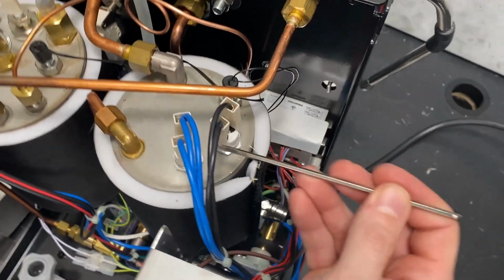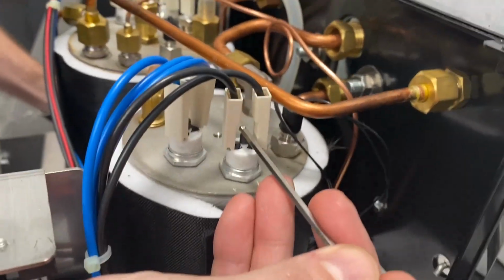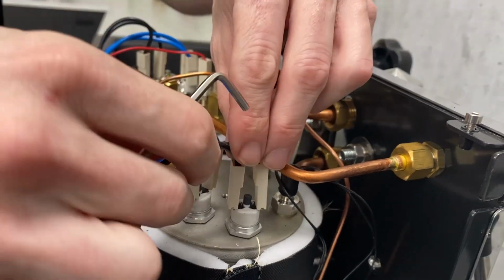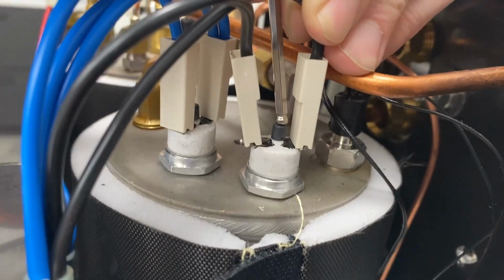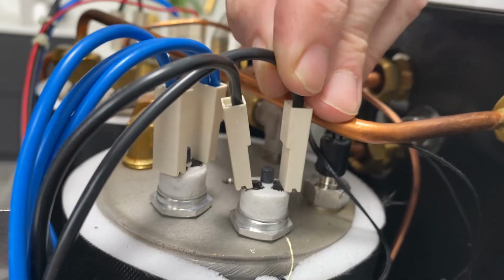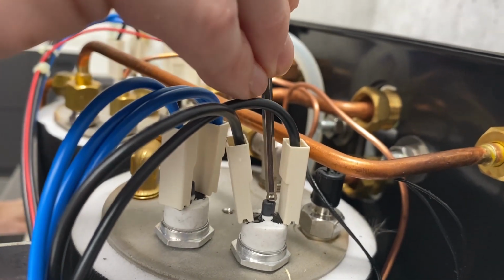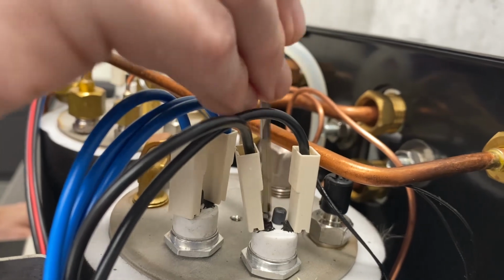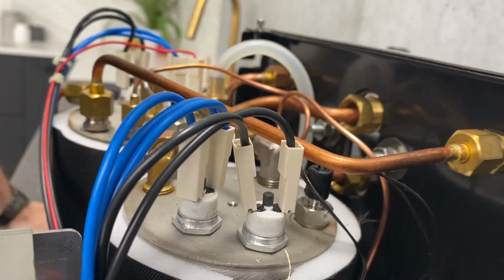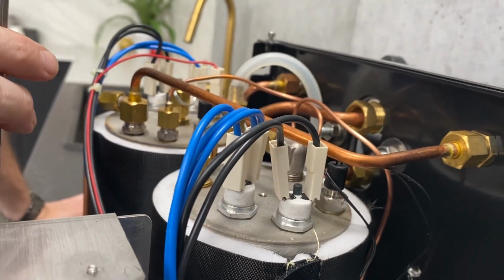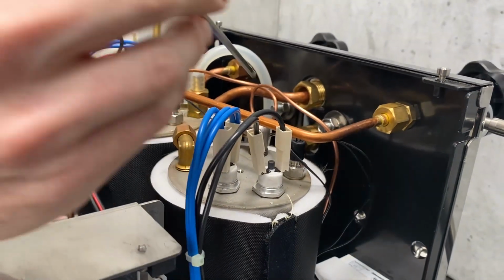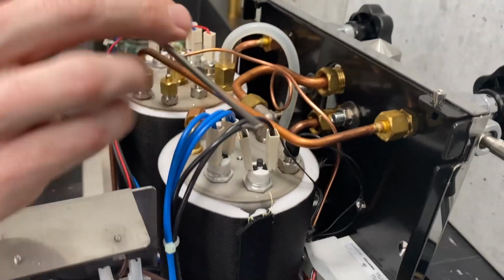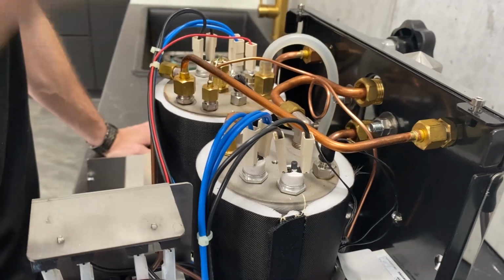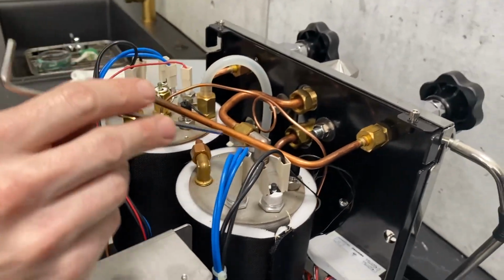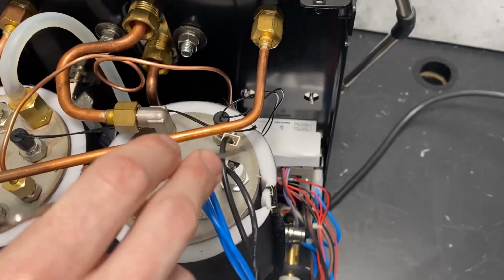You've got your two resettable stats, one for the load line, one for the neutral. If one of these ever trips, you just press on this little black switch, you'll feel a small tactile click, and that's how you know it's reset. It's such a light feeling you may not even notice, so just press it and see if that does the trick. If those have triggered, your boiler will not heat. Think of it like a little light switch on top of the machine, or a circuit breaker — if that's flipped, it's a no go.